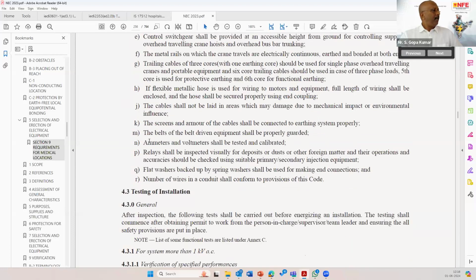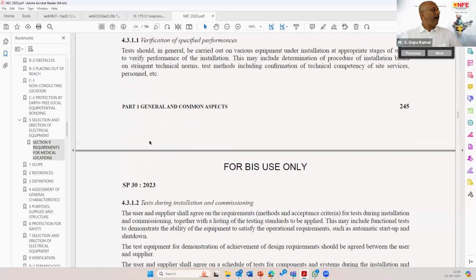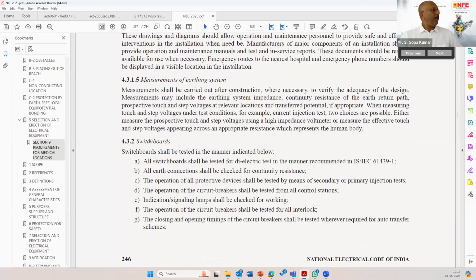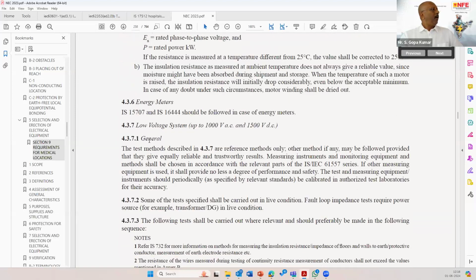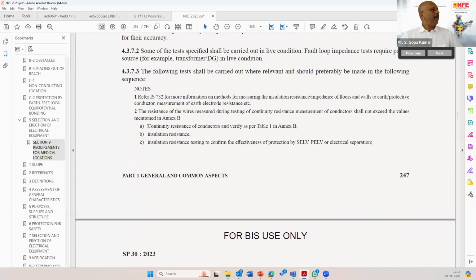After the inspection, we are supposed to go to the testing part: testing above 1 kV, and below 1 kV. Scroll down to testing 4.3.7, low voltage system up to 1000 volt AC, 1500 volt DC. You find continuity of resistance of conductors. That means if you measure the continuity resistance of the conductors, all loose contacts, including the resistance of the earth continuity conductor, will be very clear. The resistance of the wire plus the loose contacts will be clearly understood, and it's a mandatory requirement before you energize the electrical installation.